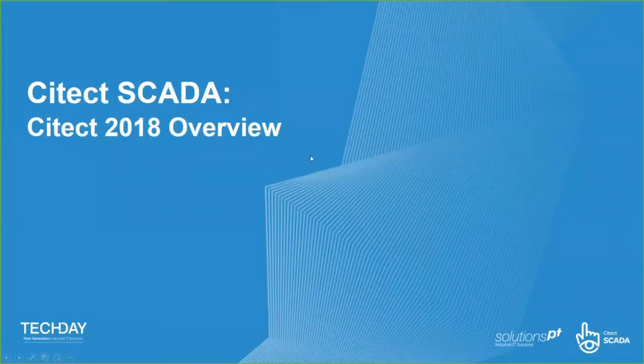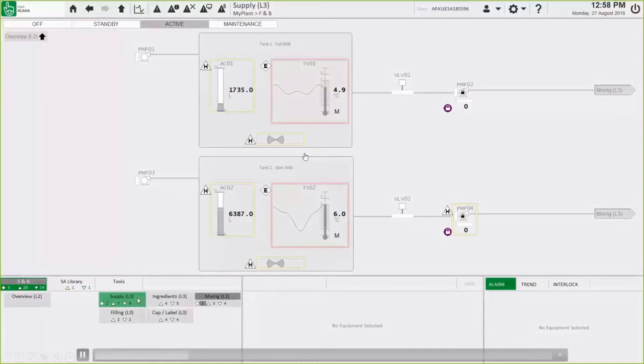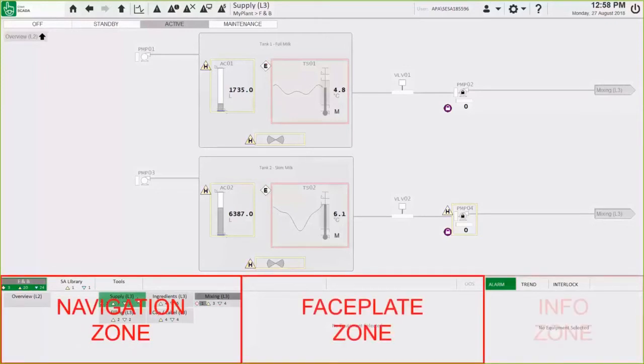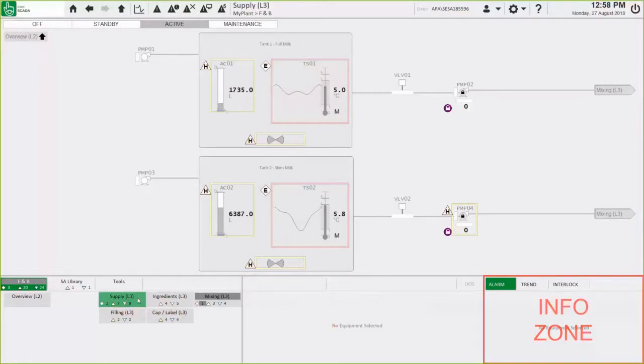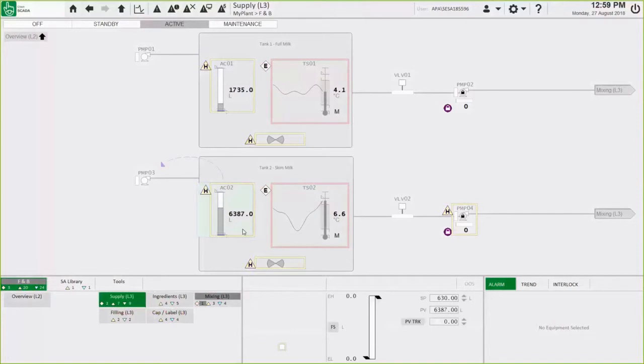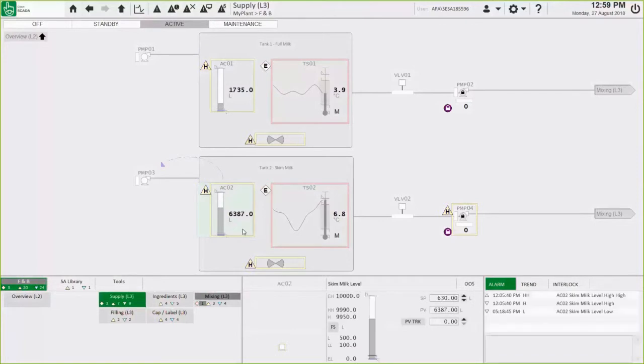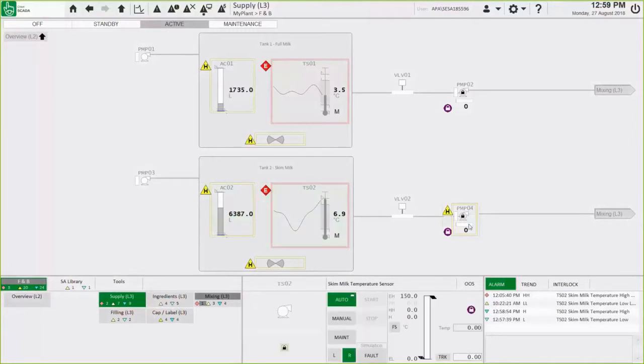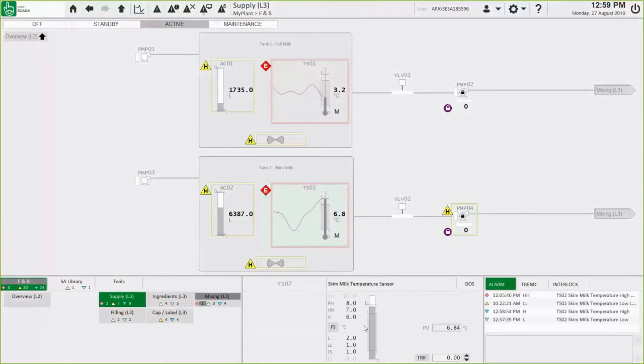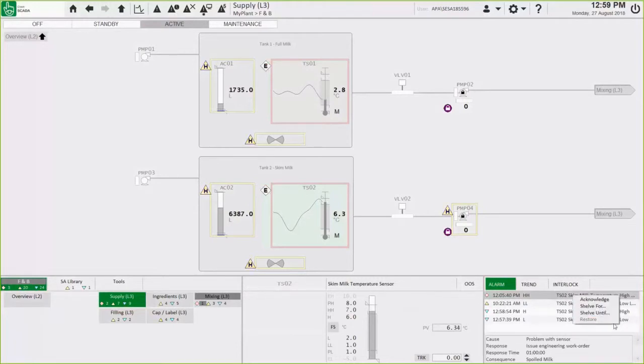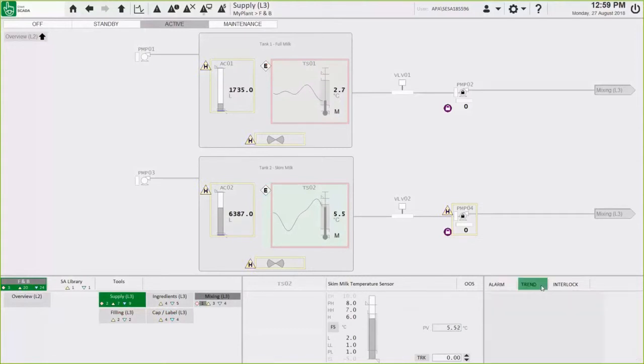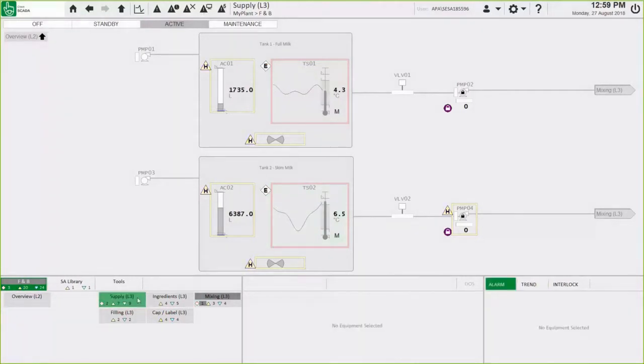Let's have a look at CITECT 2018. Here we have the example project showing the main content page, navigation, face plate, and information zone. As we select various pieces of equipment — whether it's the level instrument, temperature sensor, or pump — the face plate and alarms are shown in context. I can acknowledge and shelve alarms, and if there are trends associated to that piece of equipment I can click on the trend tab and see the specific values. If I now navigate to my alarm page...